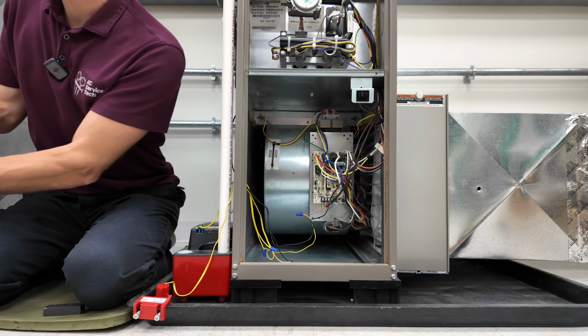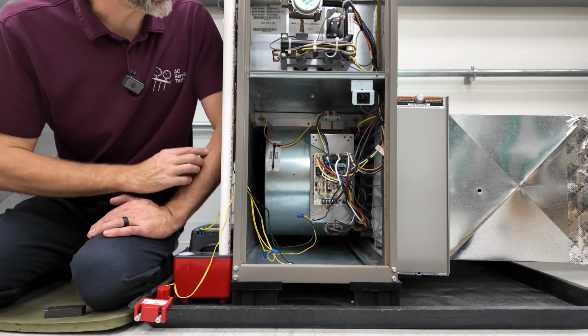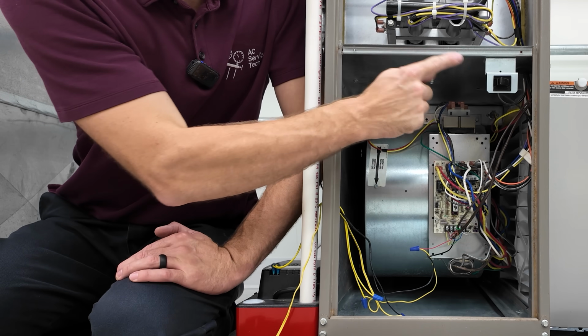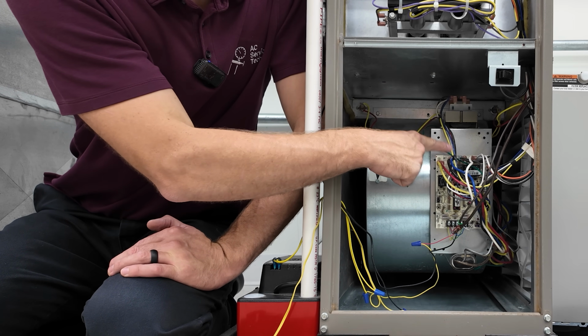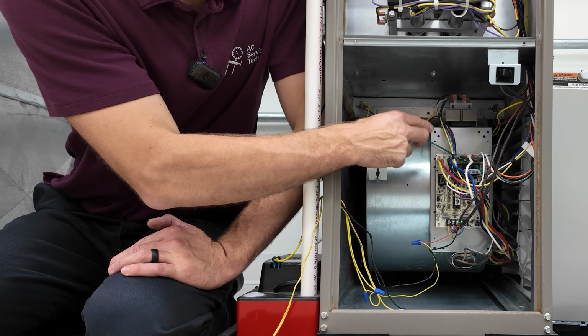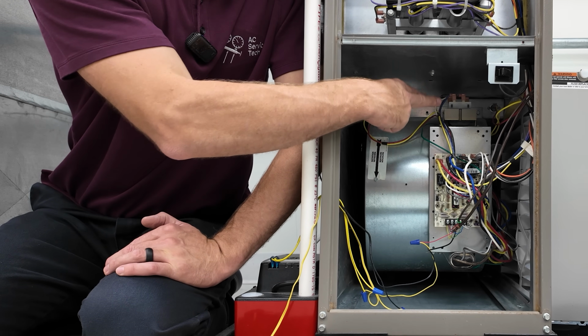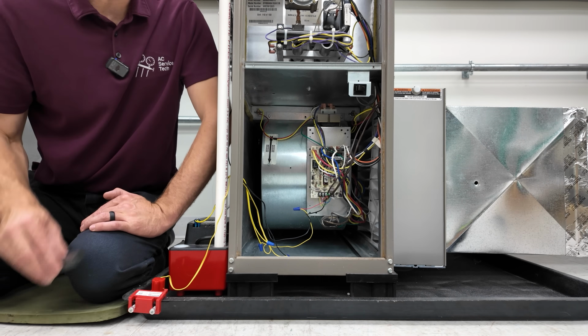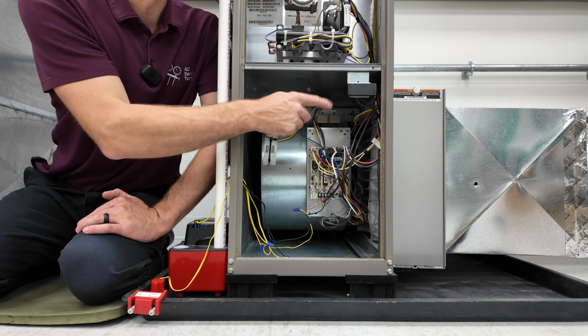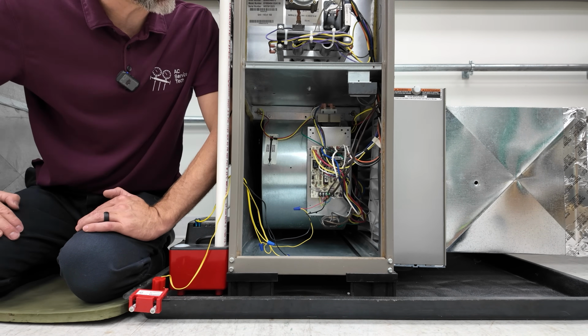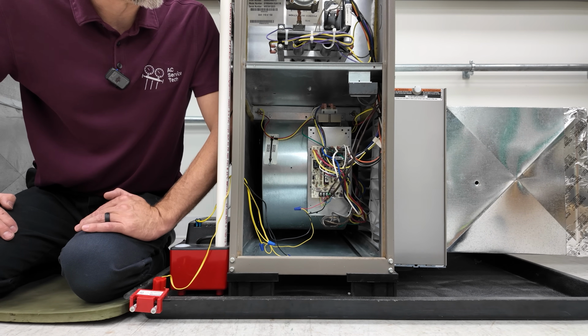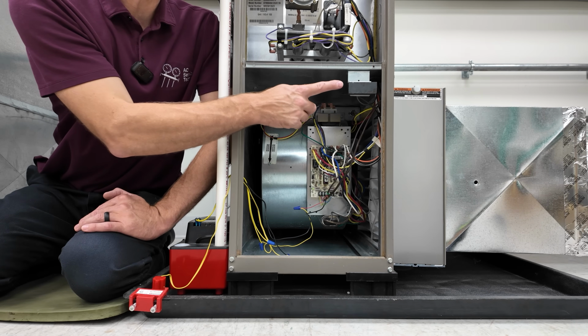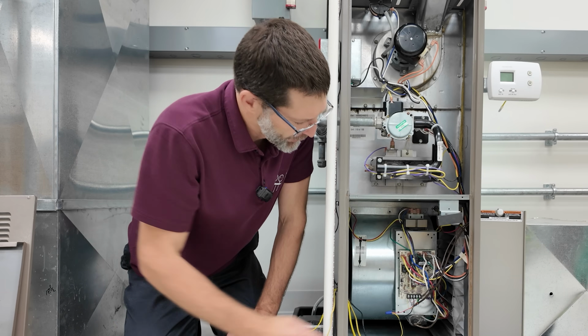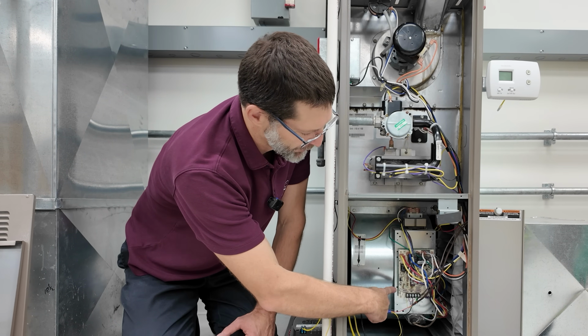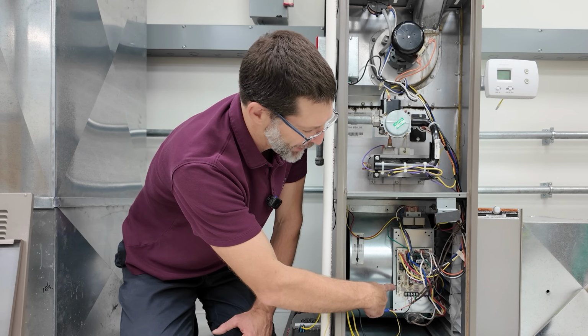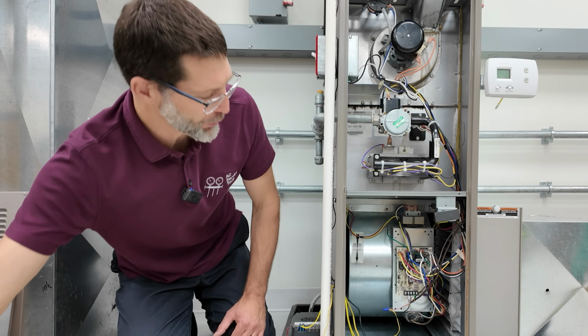So during your diagnosis, like right now, the main power is coming in from the switch up above. It comes over to here, it gets broken, and then it comes over to power the circuit board, and out of the circuit board it goes to a 24 volt transformer inside. And so that's why when you're performing service, you typically are going to use a magnet. I don't like to use tape or anything like that that's going to come off, but you're acting as if this door is in place, and it's very important to remove this magnet after you're all done. We still notice that we don't have an LED status code light, which means we don't have 24 volt power for the status code.